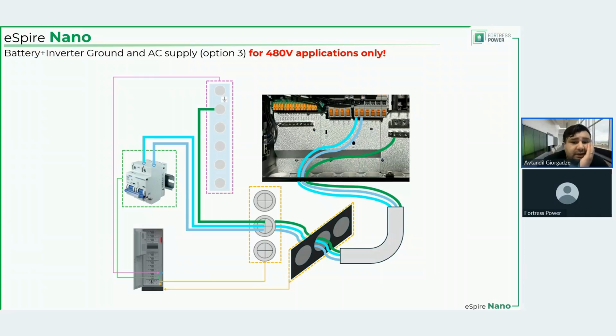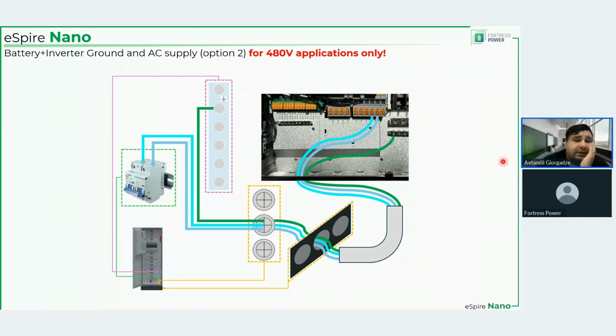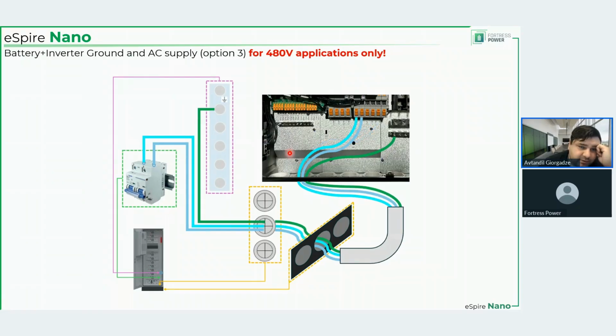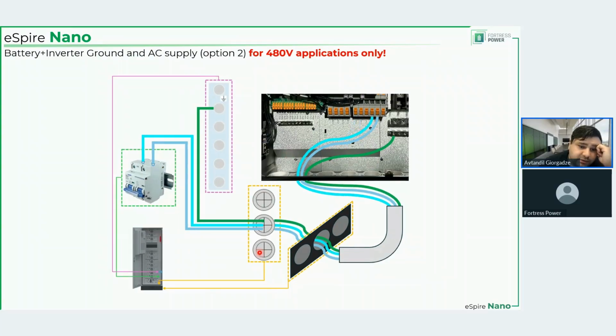In some applications, you may find yourself in a situation where smart ports are occupied, but backup ports are available. Even still, you can take the backup ports and use them to power the AC circuits of the battery unit. And just like before, you're going to use the second knockout, or middle knockout, on the plate and the middle rubberized inlet on the battery unit. And ground, obviously, the ground bar connects to the inverter ground. There's also option number 3, and I made a slight mistake. This one is labeled as option number 3. This is option number 1. This is option number 2, and this is option number 3.